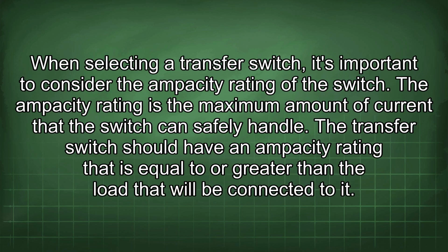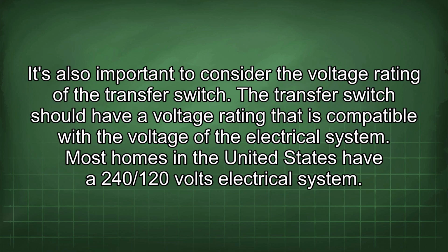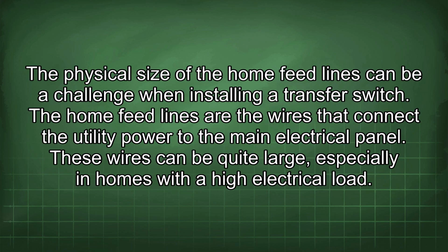When selecting a transfer switch, it's important to consider the ampacity rating of the switch. The ampacity rating is the maximum amount of current that the switch can safely handle. The transfer switch should have an ampacity rating that is equal to or greater than the load that will be connected to it. It's also important to consider the voltage rating of the transfer switch. The transfer switch should have a voltage rating that is compatible with the voltage of the electrical system. Most homes in the United States have a 240/120 volts electrical system.